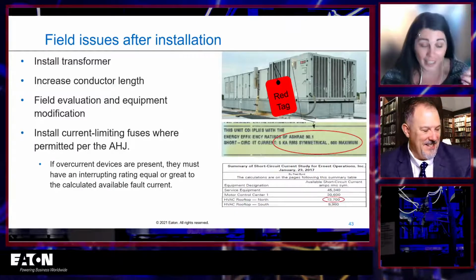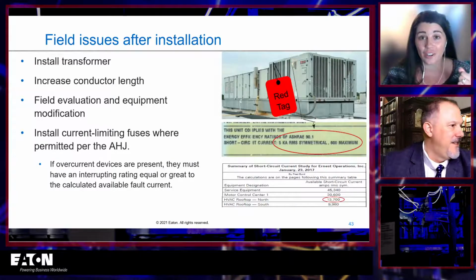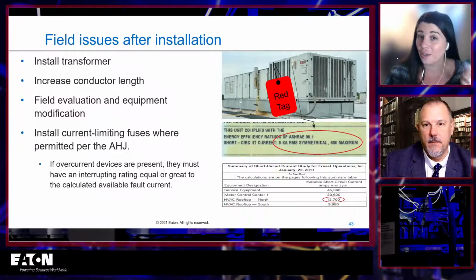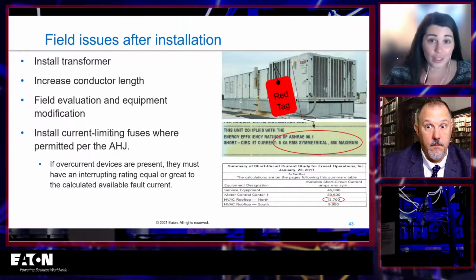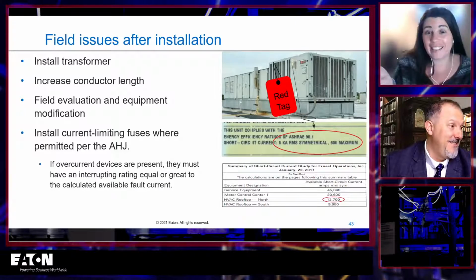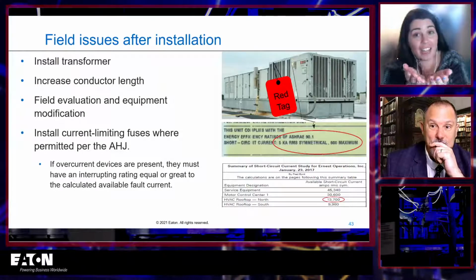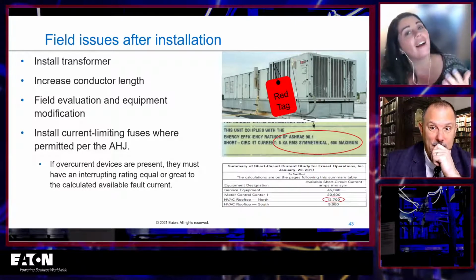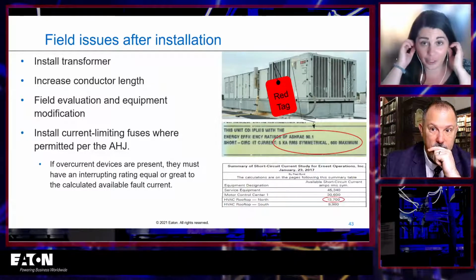And generally speaking, you've got two solutions, right? If the short circuit current rating is lower than the available fault current, you can either raise the short circuit current rating or lower the available fault current. That's it. They eventually have to be a certain way.